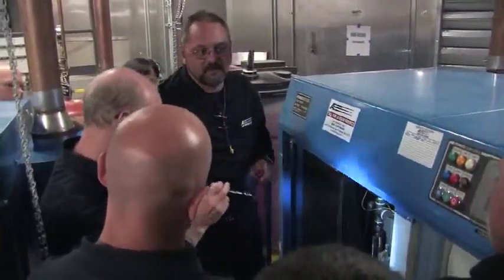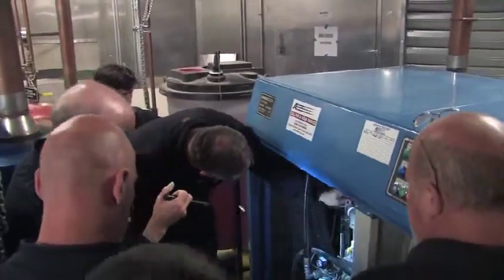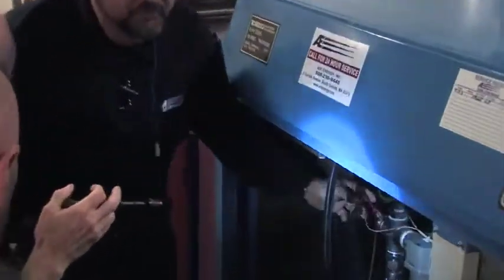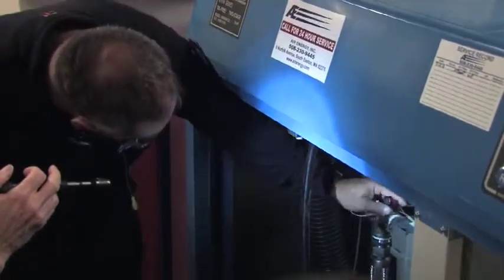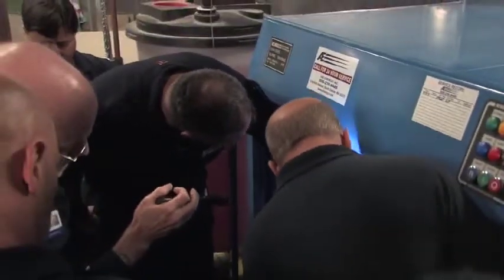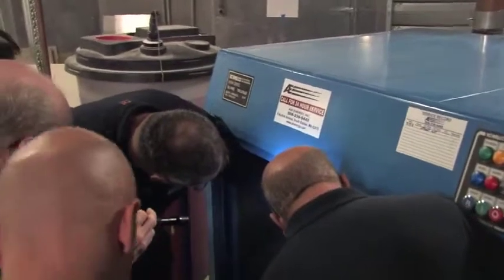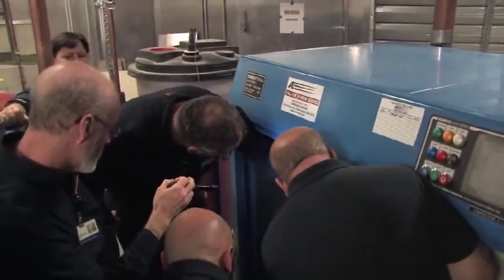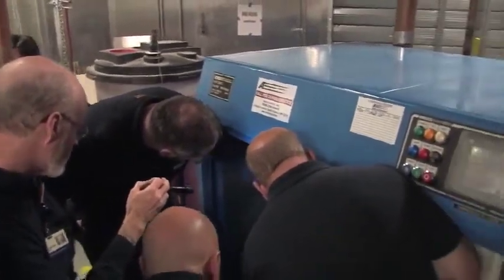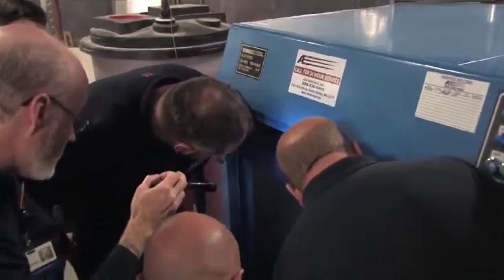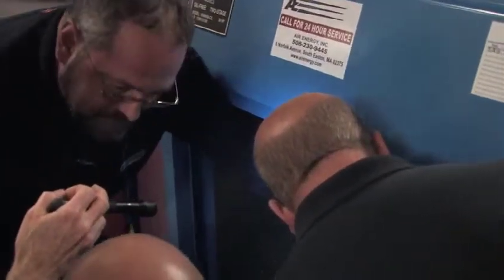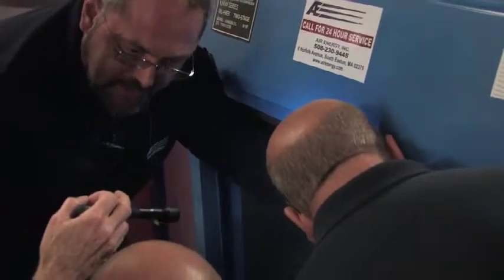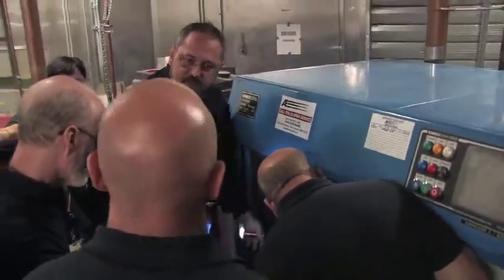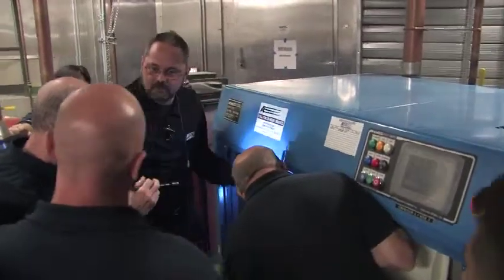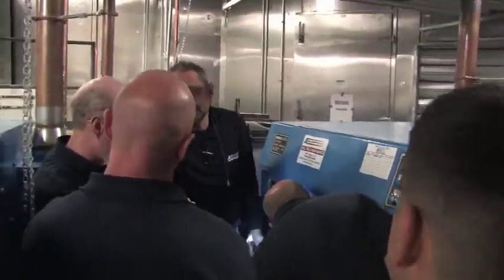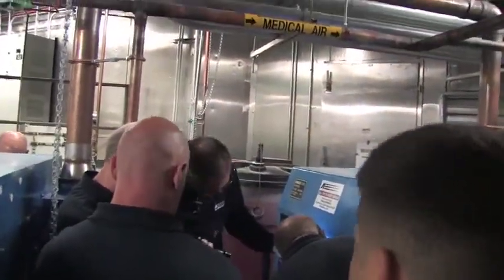Very good. Now, when we retrofit them, rather than trying to drill and tap a hole in the base of the sump, we put them up like this. But what we end up doing is we basically put the drain line where that elbow is. We'll put a T there. So you take the elbow out and you put a T in? Yep. So the drain will drain. Basically, it'll come off where it collects. Now, of course, it can't do that when the machine's running and there's positive pressure going out. But as soon as the machine shuts down, gravity will just bring it back in. Oh, cool. Good deal.